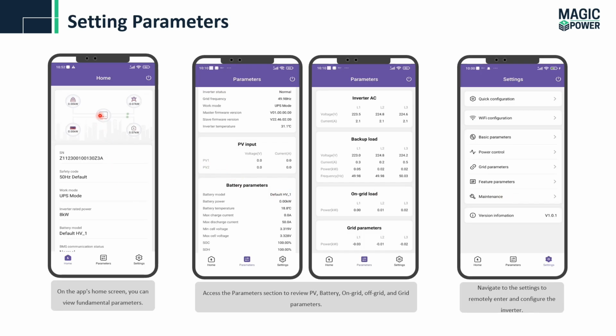We can see the energy flow diagram, PV information, battery information, grid, and load information. So the working mode of the system, the rated power of the system, and the battery connected to the system. Similarly, if you move to the parameters, we can see multiple parameters for the PV, battery, inverter, backup load, the grid side, and some grid parameters. In batteries, we can see the state of charge, state of health, voltage, current, and temperature.